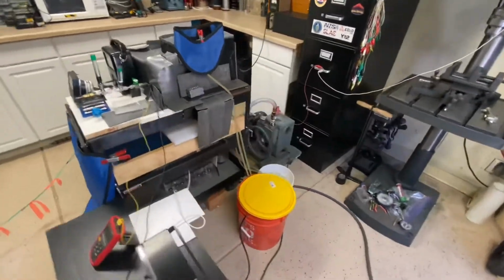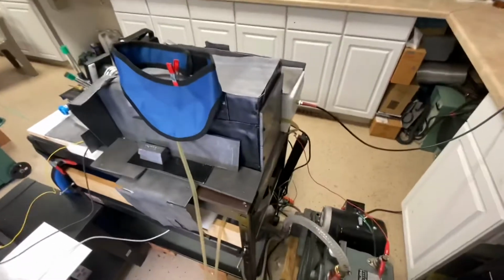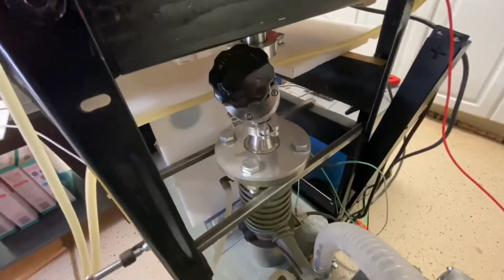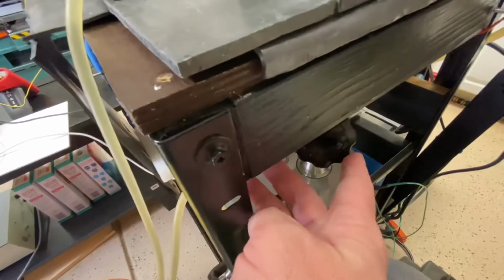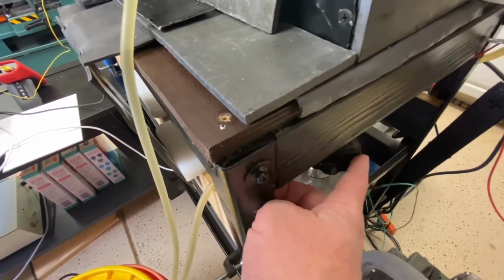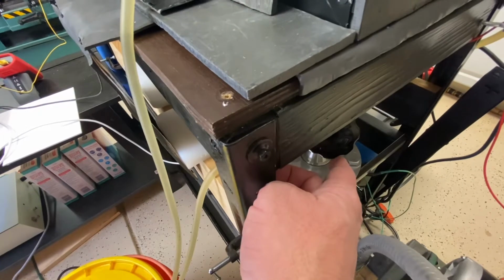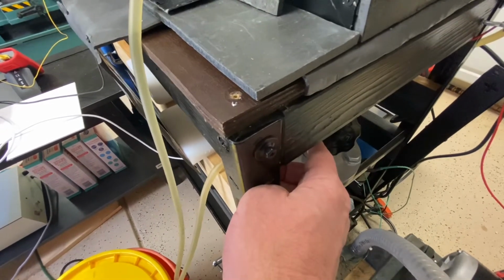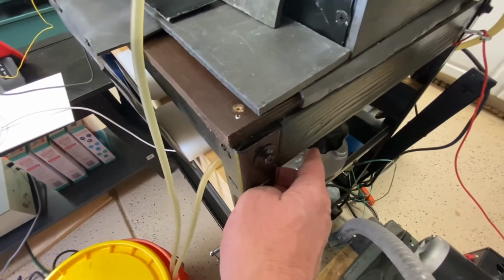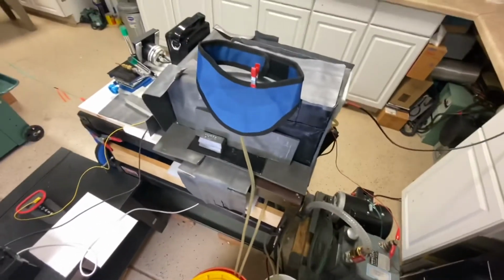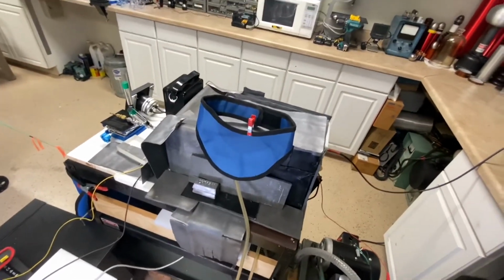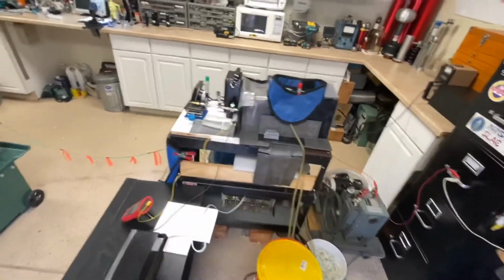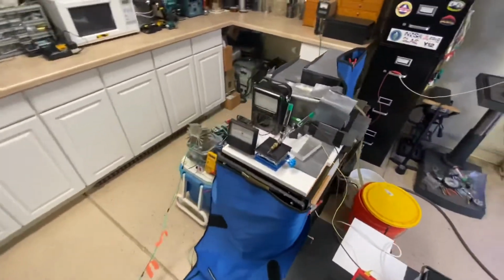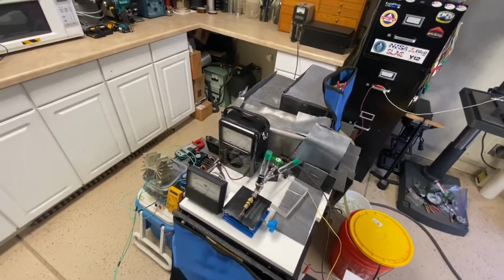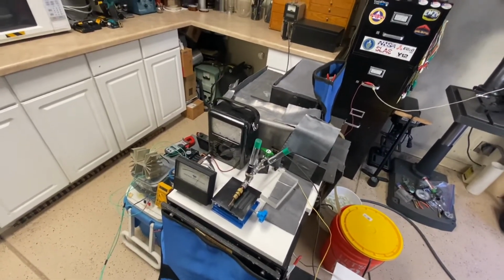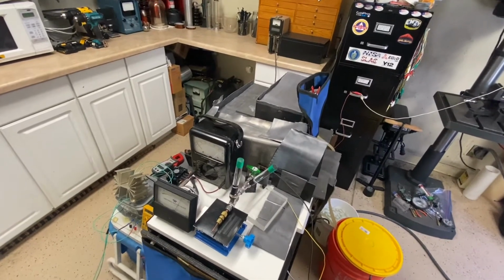So I have found that on the throttle valve down here for the diffusion pump, what you want to do is close this thing off completely once the diffusion pump has hit its proper vacuum, and then turn the knob counterclockwise just about 2.5 to 3 times. That is just about the sweet spot for getting the differential pumping completely set up for this fusor, at least to make it operate properly. Anything less than that, if you only open it up about 1 turn or 1.5 turns, it's just not going to do it.